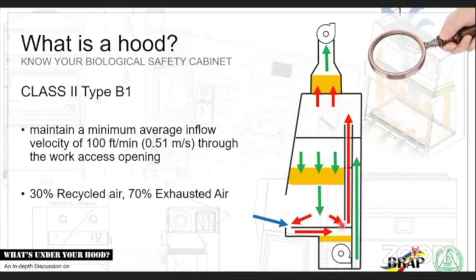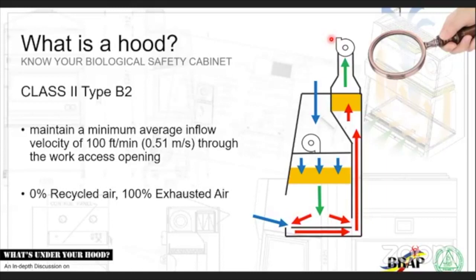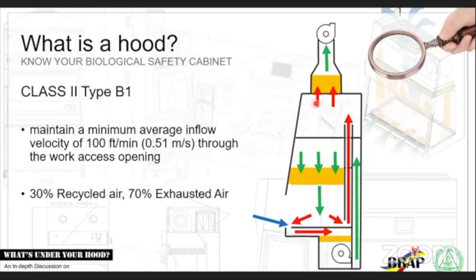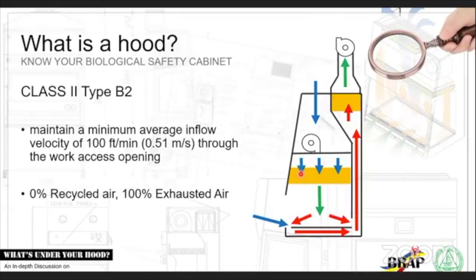Now the rear duct, this is where you work most probably, and most of the infectious materials, if aerosolized, will be sucked up to this plenum, which is negatively pressured, and get sucked through a biosafety filter outside and blown by your blower outside. Now, this one is attached to one of your ducting, hard ducting, going outside of the building. So that's your B1. Now, this is your B2. If you can see the differences, your B1 actually recycles 30% air, and 70% is exhausted. That is for B1. So the next one, for the B2, all air is exhausted. Nothing is recycled.